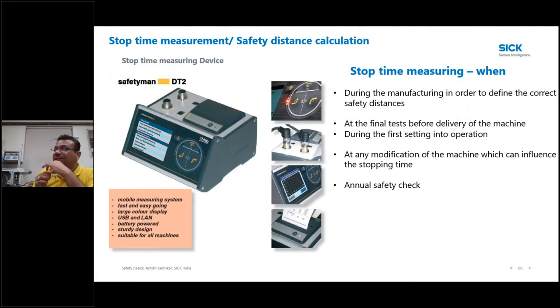We are using this machine, and the good part, the beauty of it, is that we are not going to disturb your control system or machine dynamics at all. It is connected externally. The good part is that with this machine, we can get the real time total stop time of the entire machine, which includes the protective device, relays, contactors, motors, PLC and all.